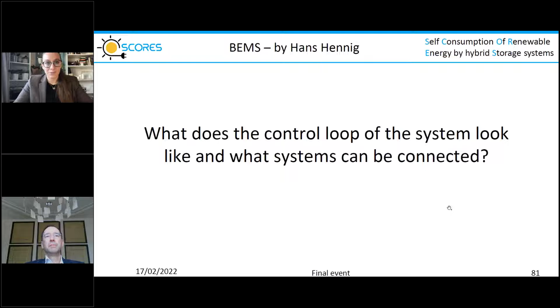Follow-up question: what happens when we want to connect a non-standard device to the BEMS? Well, the BEMS is made out of modules, and every module, for example a heat pump or a CLC, has a separate module. Once extra or other equipment is connected, we have to insert a new module into the BEM system. That module can contain either anything standard, or we can program it ourselves to mimic the behavior of the equipment in question. So you can change a system that's already running, update it, or map reality. Because it's modular, you simply put it in, and the BEMS will see it has a new module and this equipment, and take that into account in its decision.